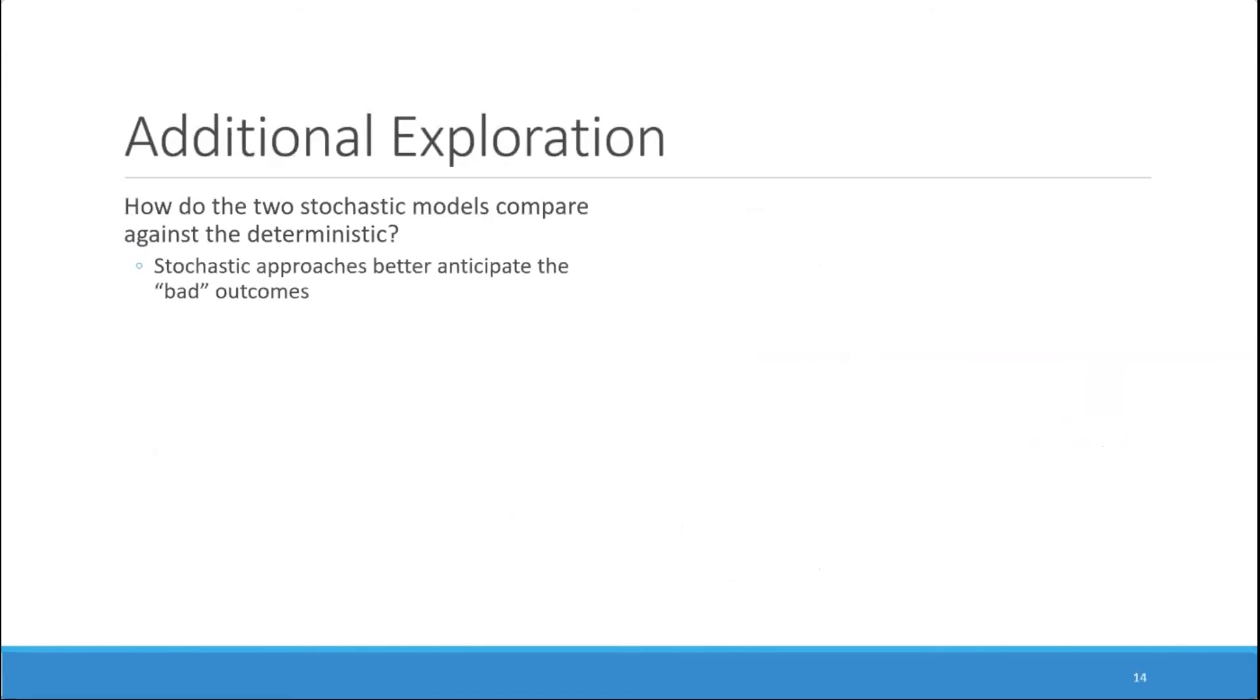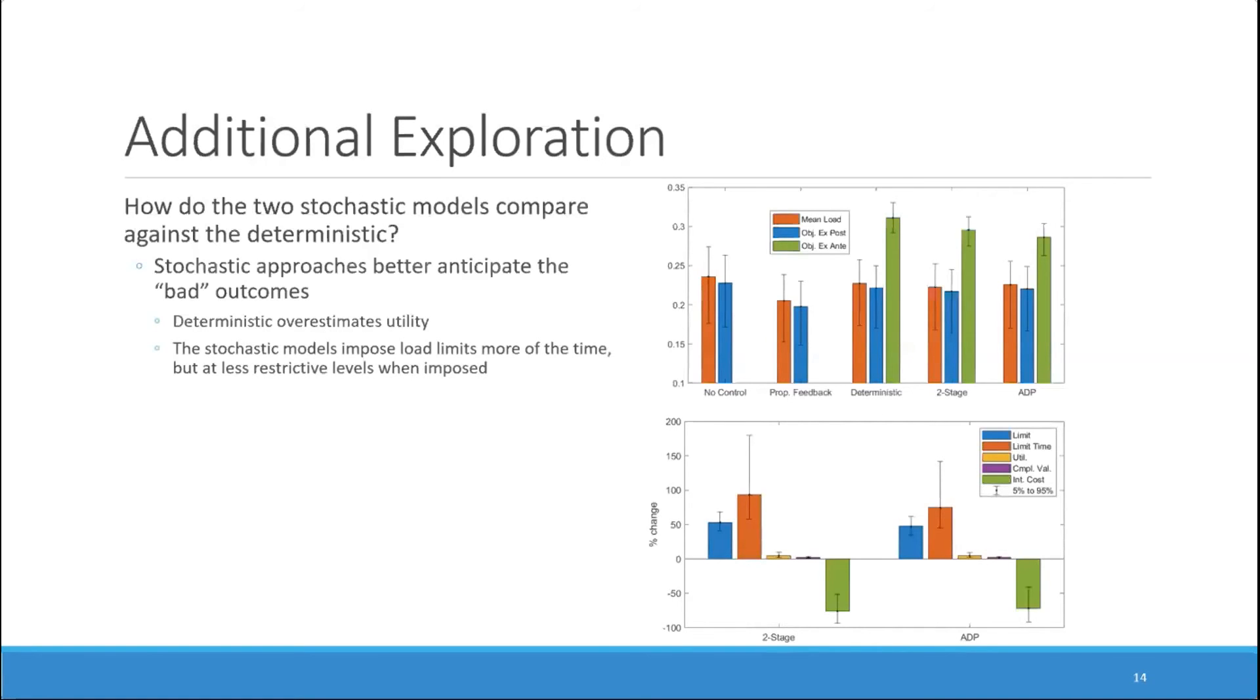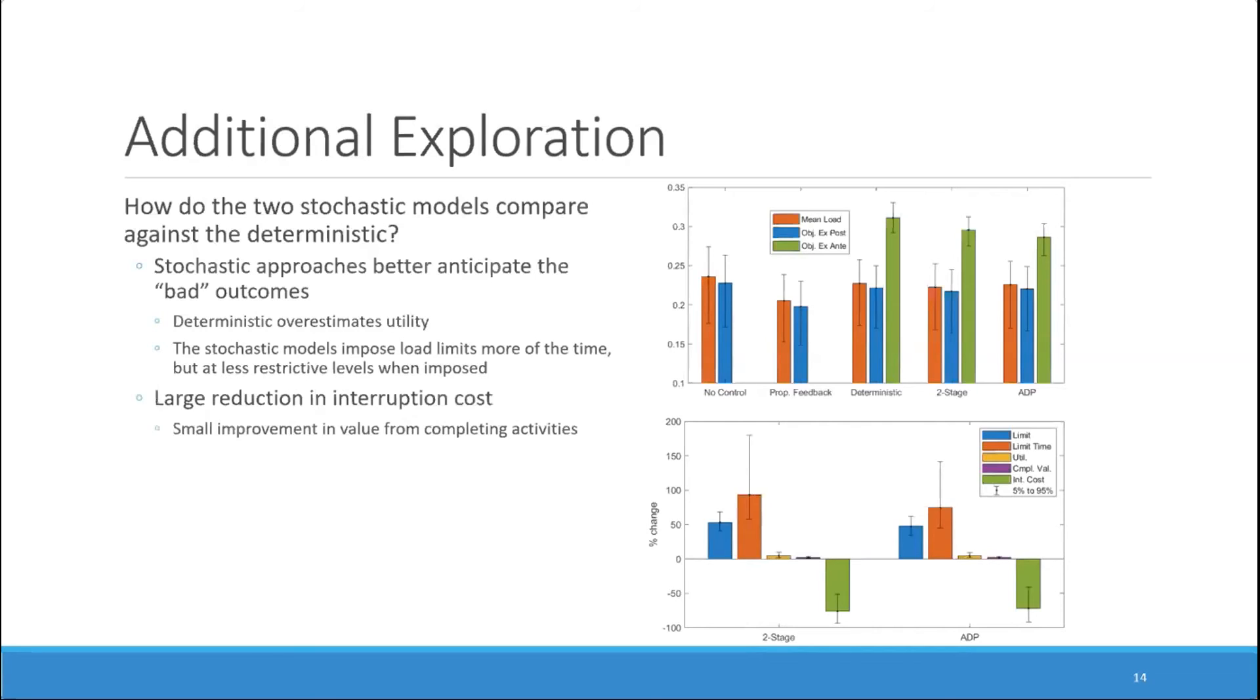We also investigated how the two stochastic models compare against the deterministic. As you may expect, the stochastic approaches better anticipate the bad outcomes. You can see here that the deterministic model overestimates the utility. This is shown in the graph that it predicts a higher value of the objective than either the two-stage or the approximate dynamic programming approach. We also see that the stochastic models impose load limits more of the time, but at less restrictive levels when imposed. Shown by the increased percent change in both the load limit itself and the percentage of time that the load limit is instated. Related to this, there's a large reduction in interruption cost in the stochastic models and only very small improvements in the value from completing activities.